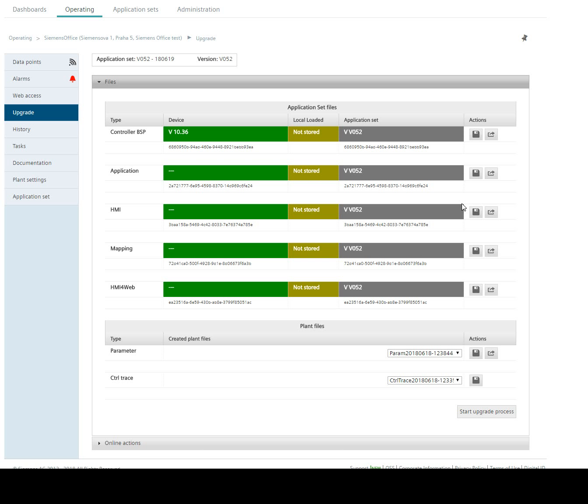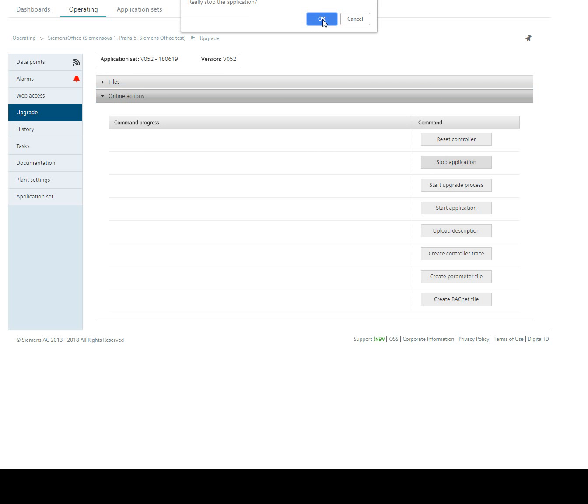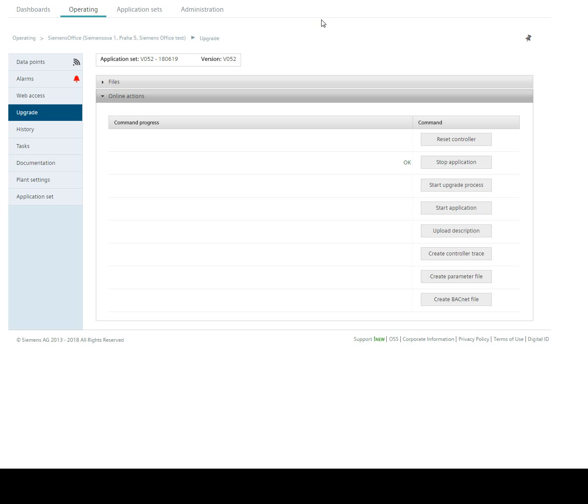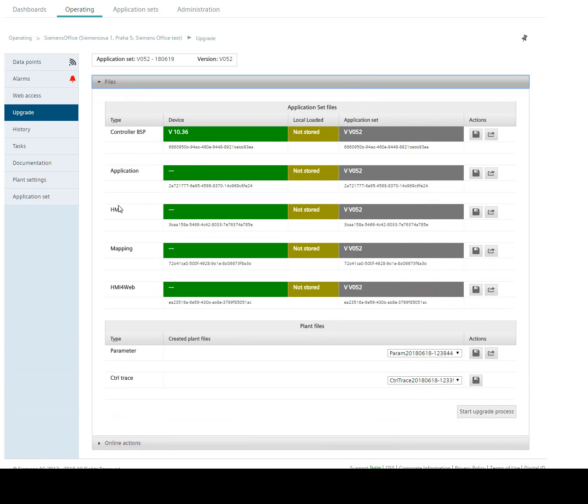In case that I want to upgrade, the approach is the same. So firstly if I want to upgrade for example only the HMI, I go to online action and I press the button stop application and yes in the pop-up window which was on the top. And I am waiting, and now the PLC is in stop mode. The application is not running.